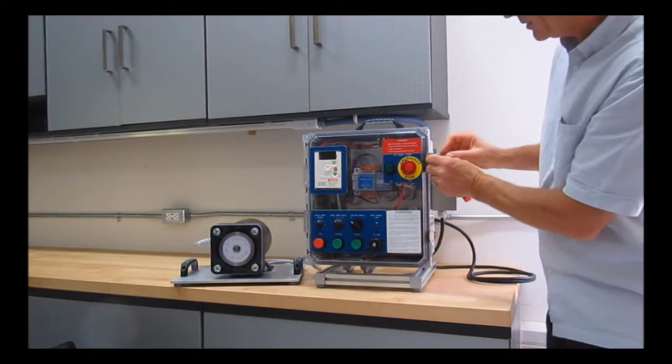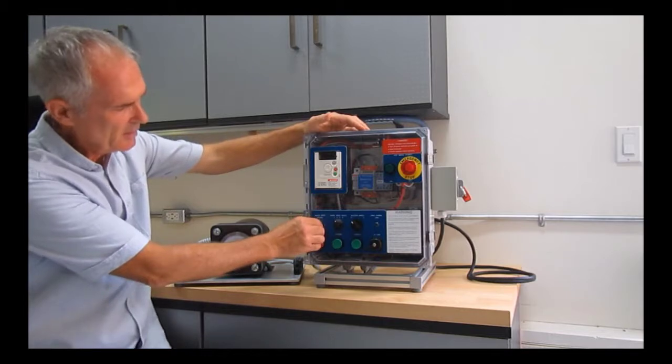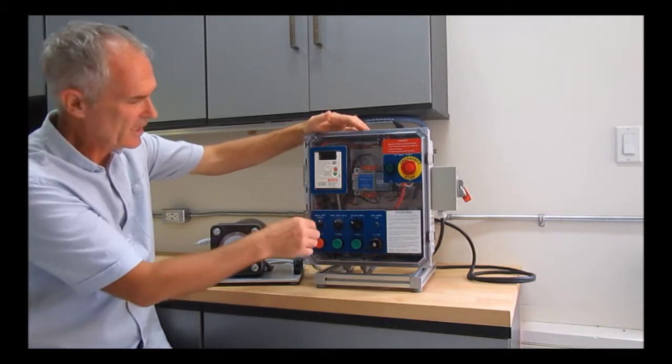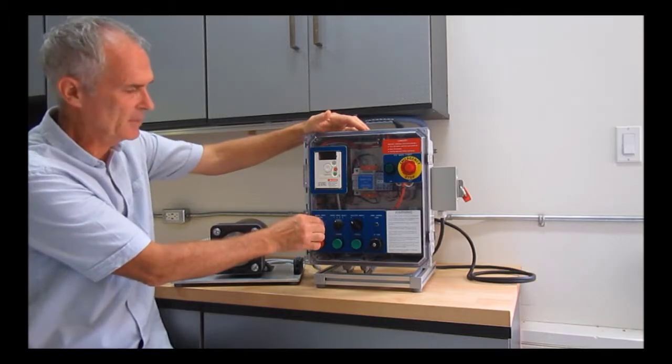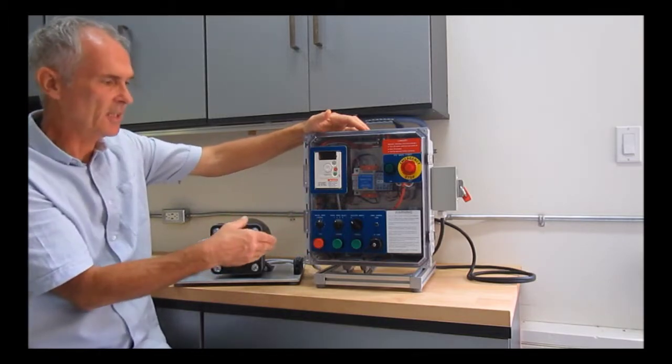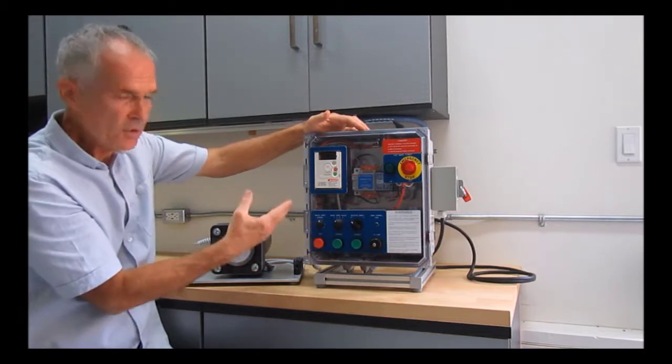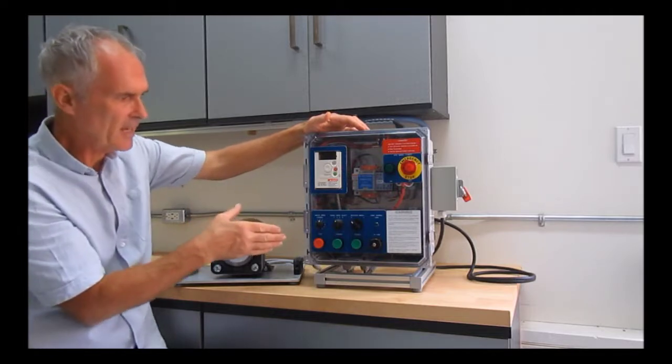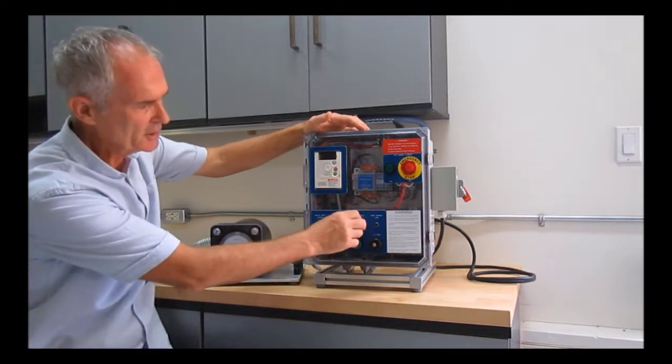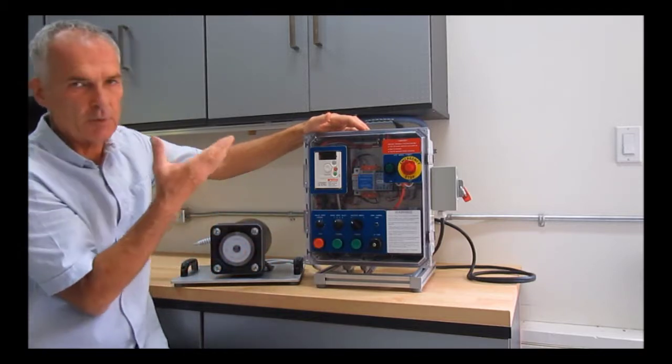We have this operator plate with an analog potentiometer - a 10k pot, heavy duty, typical potentiometer found in the industry for controlling the speed of a drive. We have a four-position binary coded switch used for digital speed control. We have a selector switch in the key position for two-wire control circuit, so it would simulate a pressure switch, temperature actuated switch, or any device like a flow switch active on and deactive on.